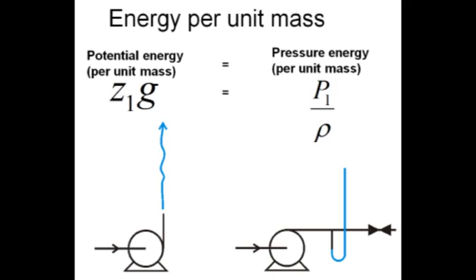And it was about 0.8 of a bar. So if we think back to this diagram again, concentrating on the diagram on the right, instead of having the manometer on the pump discharge, think about what happens on the pump suction side. Obviously now, instead of a pressure, we've got a vacuum on that suction side of the pump. You could imagine the pump situated at the top of the stairs.